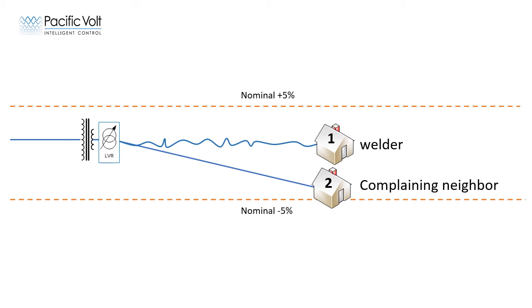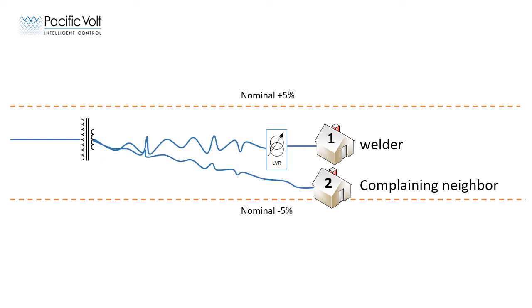So placing the LVR at the transformer will correct the voltage fluctuations in the transformer and house 2. However, it will not totally correct flicker at house 1 because of the uncorrected voltage drop in the conductors feeding the house, which is causing the problem. Putting an LVR at house number 1 will mitigate their flicker complaint. However, it does not change the rapid load fluctuations, which are still causing lesser voltage drops in the transformer that are being transferred directly to house number 2.